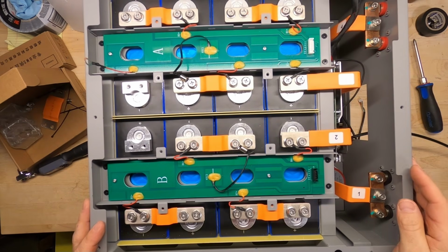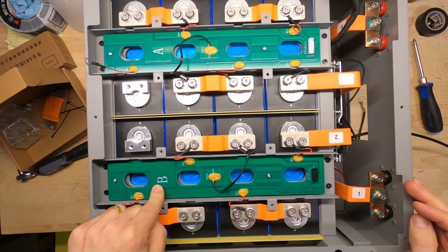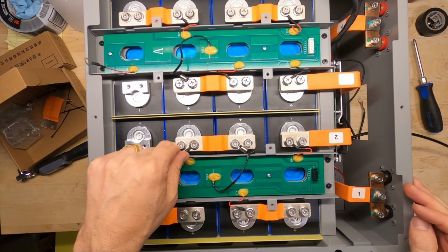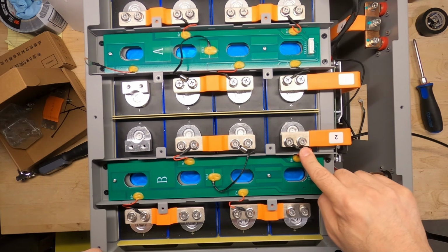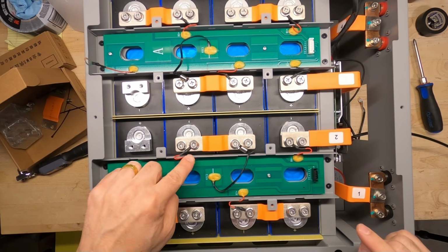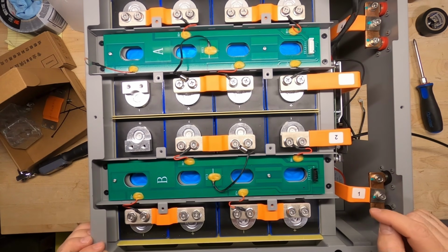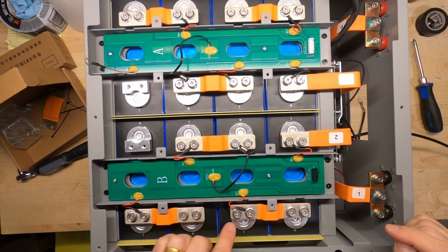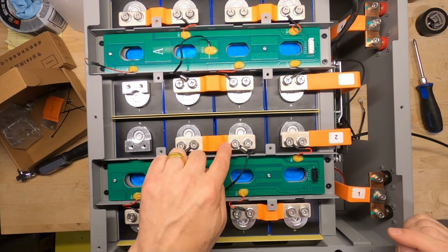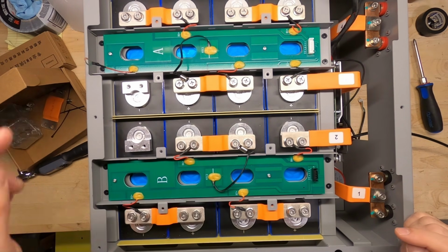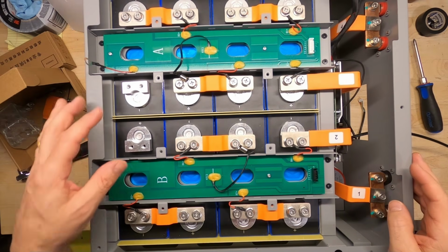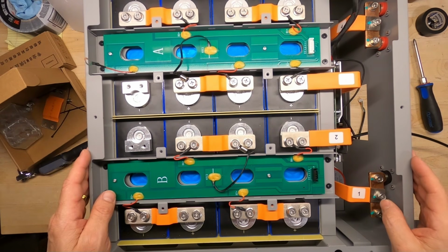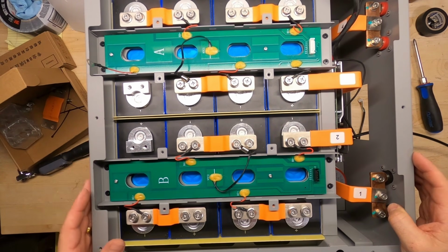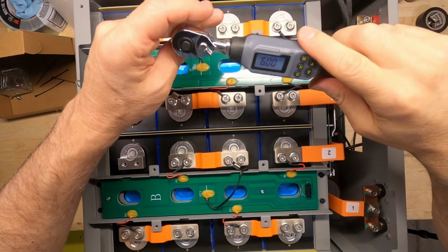Okay, I finished putting all the balance leads on the B PCB. So we got cell 8, 7, 6. And I put the missing screws in the rest of the bus bars. So all we have to do now is put our bridge bus bar in and torque the bolts down. This time I'm going for 6 Newton meters.